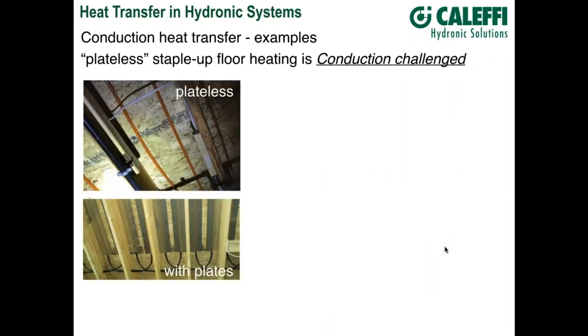Here's another situation that comes up a lot: what I refer to as a plateless staple-up system. That photo shows the underside of a floor deck with half-inch tubing stapled to the subfloor, roughly eight inches on center. I'm going to contrast that with a system that has the same half-inch tubing at eight inches on center, but with six-inch-wide aluminum plates on it. How much benefit will adding those aluminum plates have?